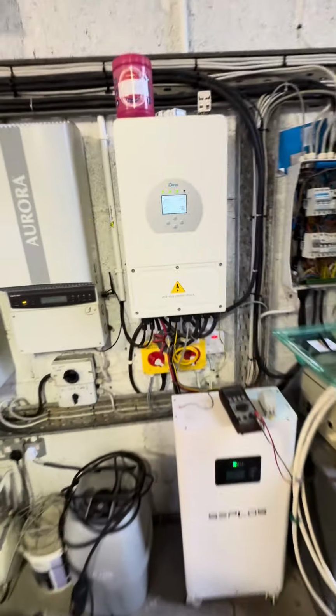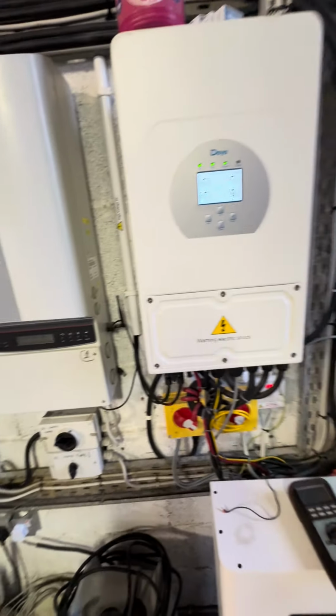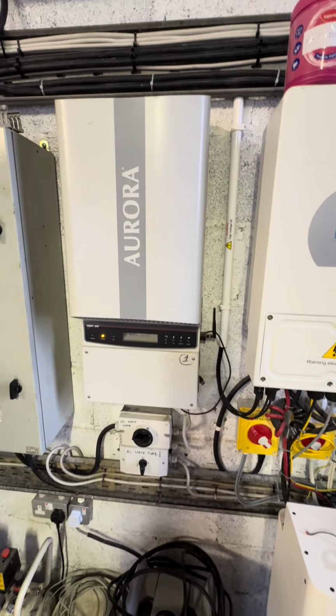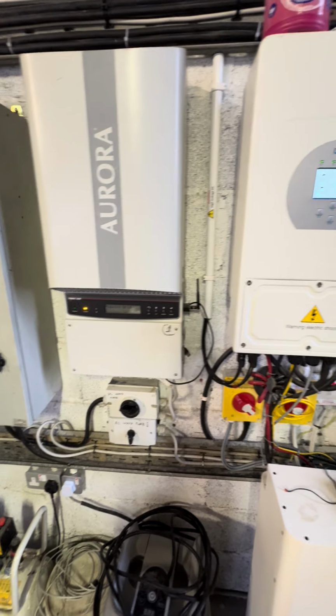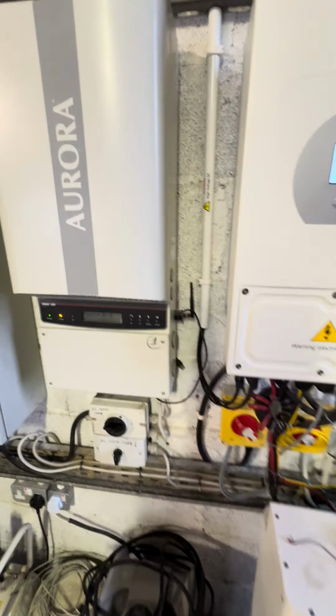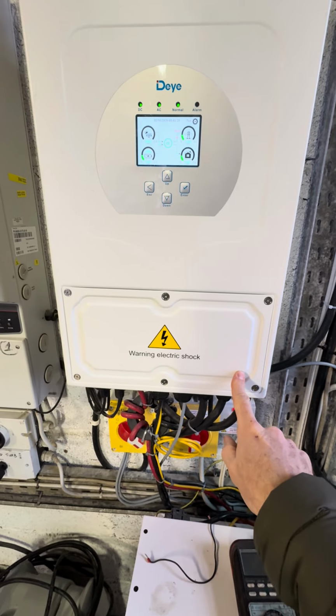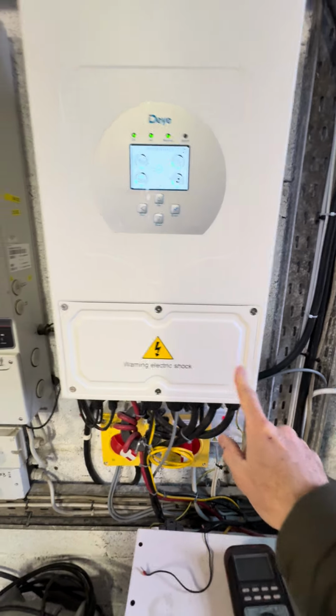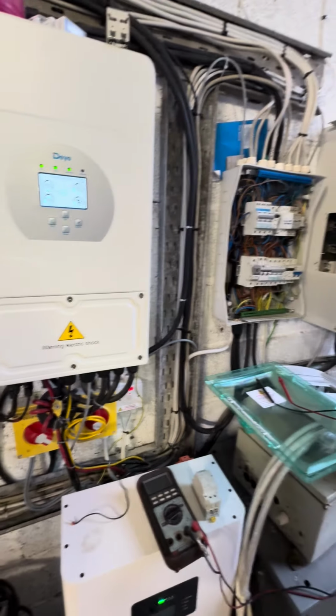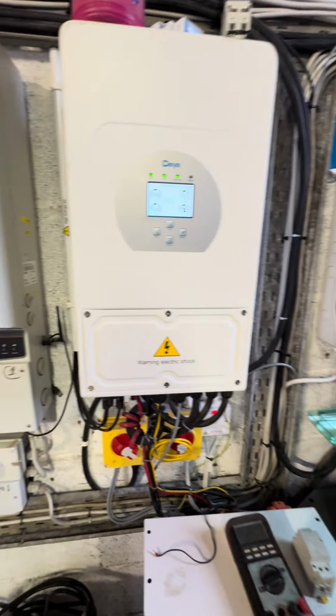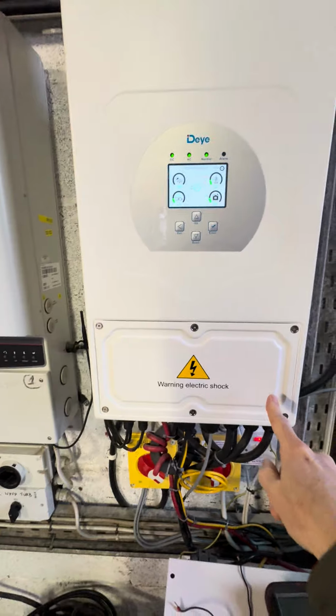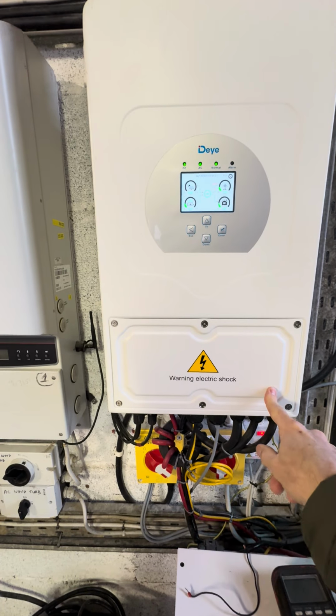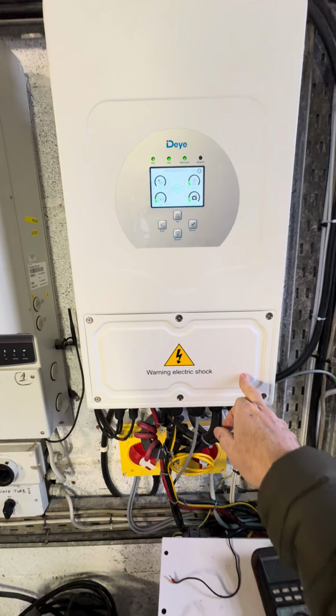Okay, time to test the off-grid and the synchronization between the Deye inverter and the Aurora and the diesel generator. I've made a couple of changes last night. I've installed a neutralizing link here in the Deye inverter. Previously I was doing it with contactors here on the board, but it wasn't working. It was causing a lot of troubles. So I've now moved the neutralizing link onto the load terminal here in the Deye inverter.